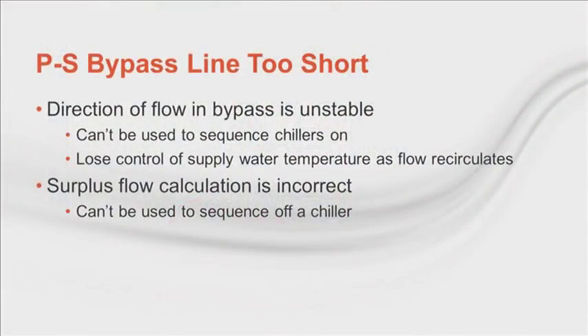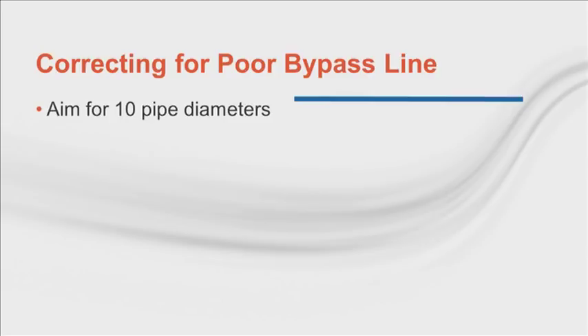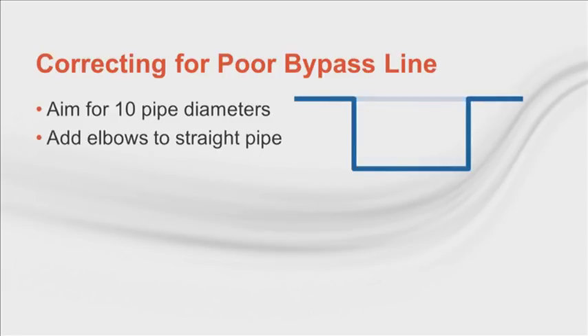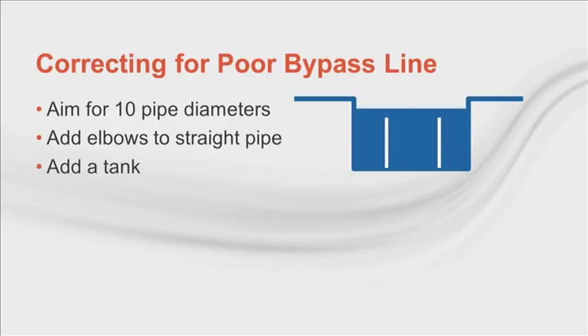We see this problem a lot. The decoupler pipe has so little pressure drop that the water short circuits, and the direction of the flow in the decoupler is not a reliable indicator of flow surplus or deficit. Both the add and subtract sequence are affected. So aim for the decoupler to be at least 10 pipe diameters of straight pipe long. If you can't do that, some of the less disruptive resolutions to the bad decoupler design include installing elbows in the decoupler to increase its pressure drop, installing a tank in the decoupler, or putting a check valve in it.